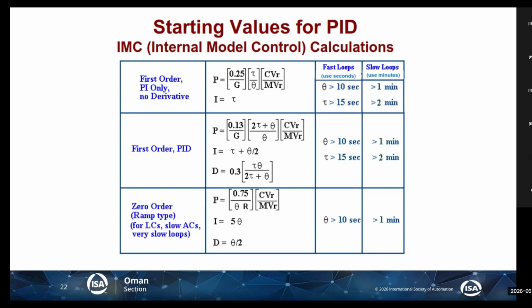There are other methods, some maybe complicated, some less complicated. I will explain this methodology also, but my recommendation, to be honest, is to use software, especially for new engineers, in which you can extract the data from the PI system or DCS and then model. You can identify dead time, time constant, process gain, everything. You can draw your model and your system in the software, and then tune offline and see the effect based on the model. If it works fine, then implement it on the DCS, especially for sensitive loops and complex loops.